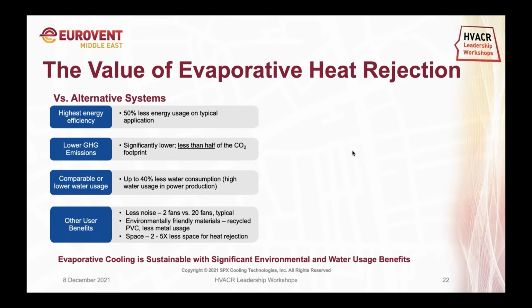The value of evaporative heat rejection versus an alternative system: you will acquire almost 50% less in terms of energy usage. Of course this is applicable for a minimum capacity - I'm not referring to a 700-800 ton project, I'm referring to large projects. You will see big differences when it comes to energy consumption.